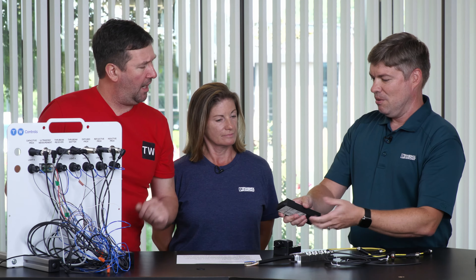Common power — which pins is that? That would be pins 1, 3, and 5, so you've got your ground in there as well. That's common throughout all of the slots. So whatever master cable you have going back to your cabinet, you're looking at three conductors to distribute all of that power to the box.